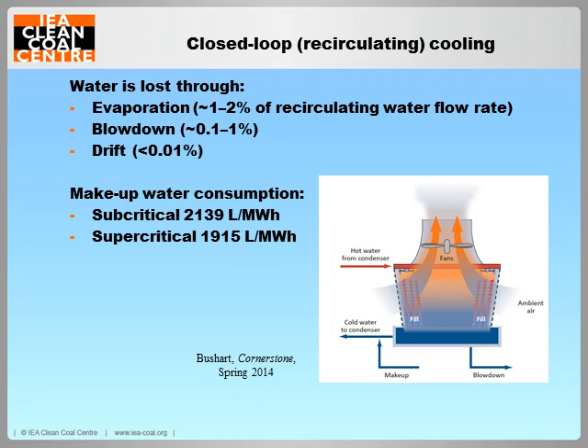Make-up water is needed to replace the water lost through evaporation, blowdown, drift and leaks. The water evaporated in the process forms a water vapour plume and exits through the top of the tower. This loss leads to the build-up of minerals and dissolved solids in the water that can adversely affect performance. So to prevent this build-up, a portion of the water, which is known as blowdown, is periodically discharged from the system. And drift is the water droplets carried out of the tower with the exhaust air.